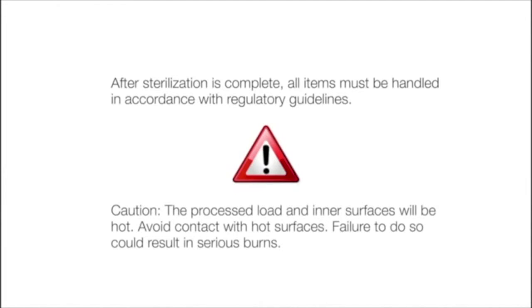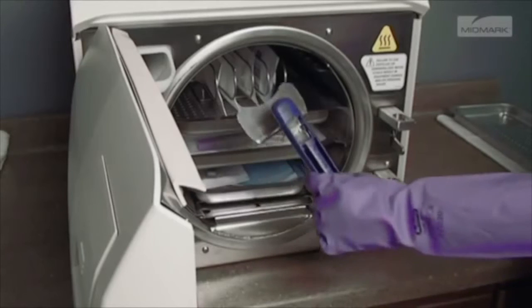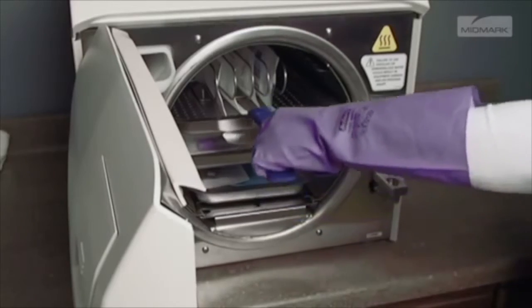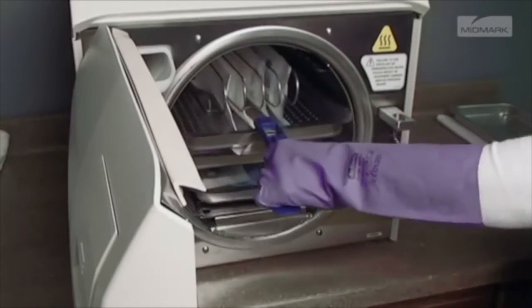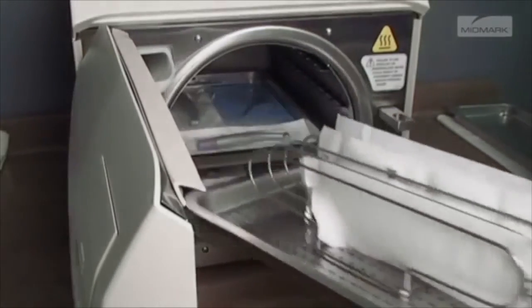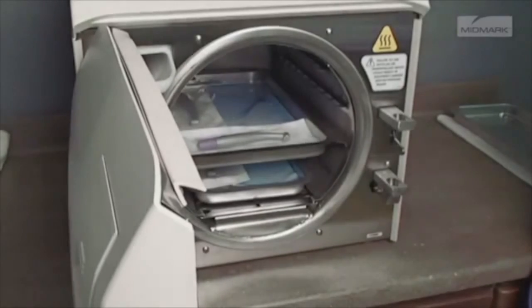Caution: the processed load and inner surfaces will be hot. Avoid contact with hot surfaces. Failure to do so could result in serious burns. Remove trays and cassettes using the Midmark Approved Tray Cassette tool. Hold the tray level and slightly elevated to prevent it from shifting and becoming dislodged.